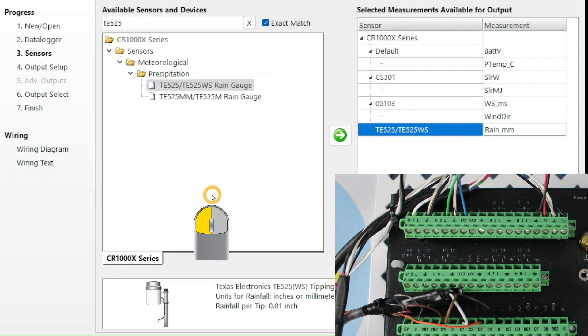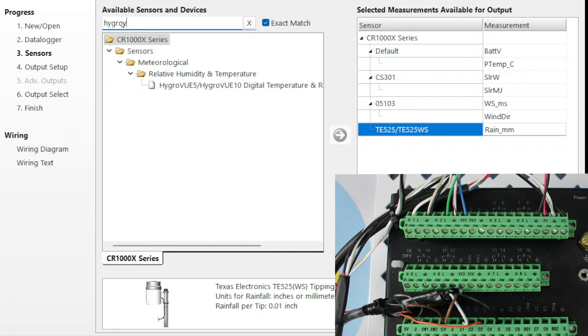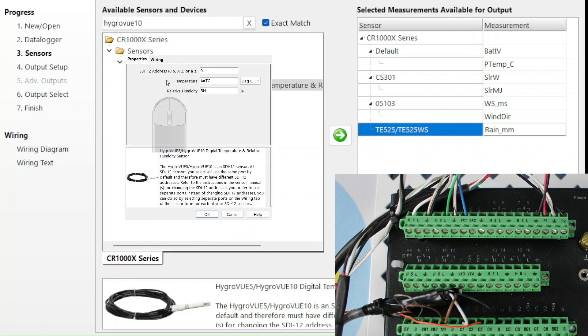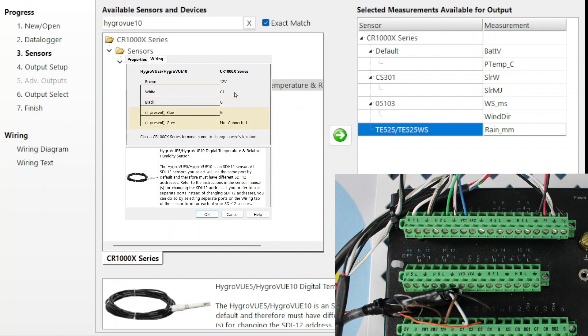Moving down to the bottom terminal strip, I see a white wire in channel C1. When I search for the HygroVUE10 and double click it, the wiring tab tells me that SCWIN assigned the brown wire to 12V, the white wire to C1, and the black wire to G. My sensor doesn't have a blue or gray wire. This matches my photo, so I select OK.